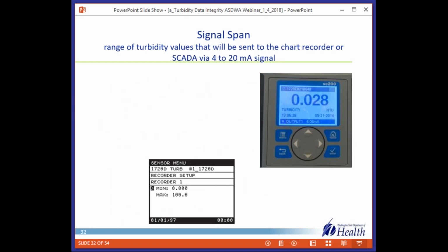One of the most important settings that we looked at was signal span. Most of the finished water turbidimeters read in the range of 0 to 100 NTU, and the signal span is the range of turbidity values that get sent to either the chart recorder or SCADA.